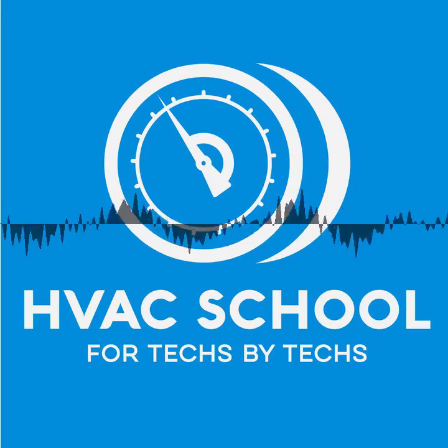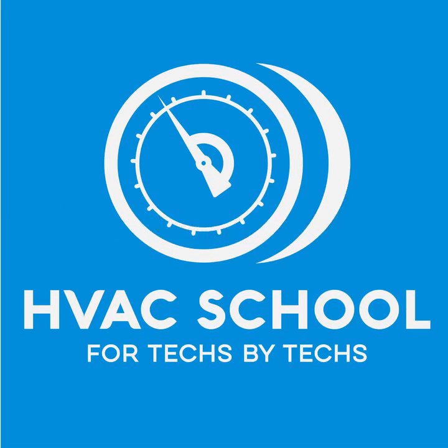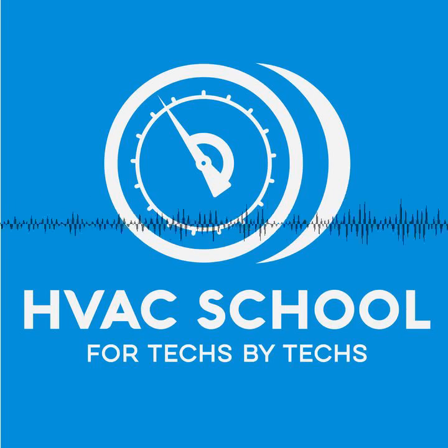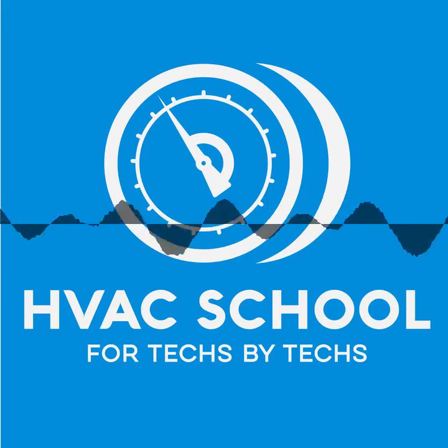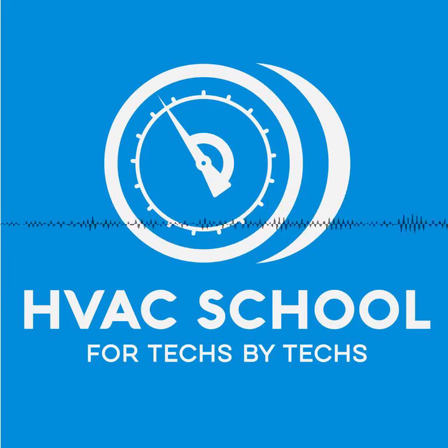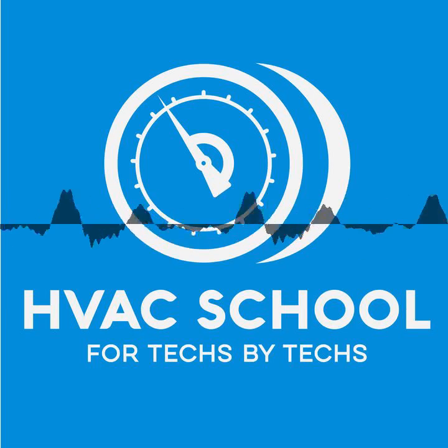So a 45-degree evaporating temperature, air conditioning situation. If your valve has 7 degrees written on the side of it, that means that it will not even start to open up until you have 7 degrees of superheat. That is the static superheat. So the valve is fully closed until you have at least 7 degrees.